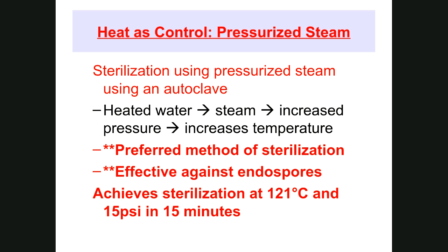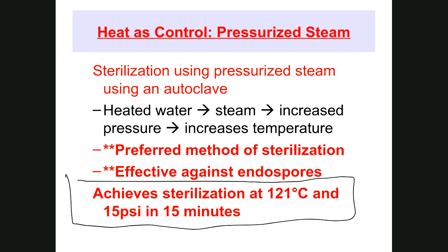Okay, so that's pasteurization. Sterilization using an autoclave, meaning pressurized steam. This is the preferred method of sterilization. You do need a special machine. You need an autoclave, which is going to use steam at high pressure to sterilize. The parameters are 121 degrees centigrade, 15 pounds per square inch of pressure, 15 minutes. And yes, you do need to know the parameters. This kills everything, including endospores.